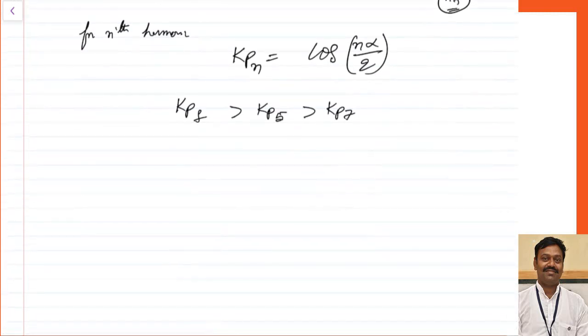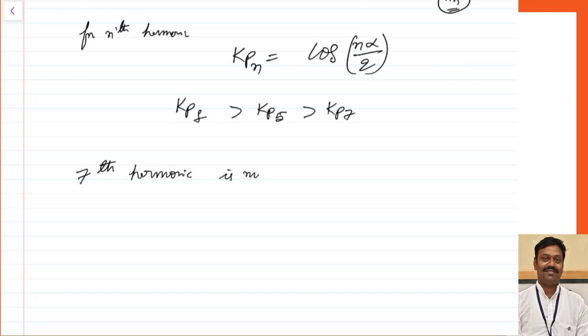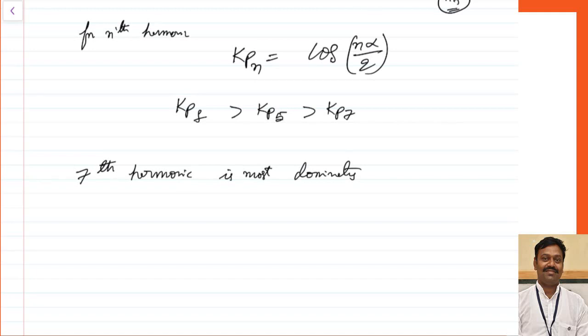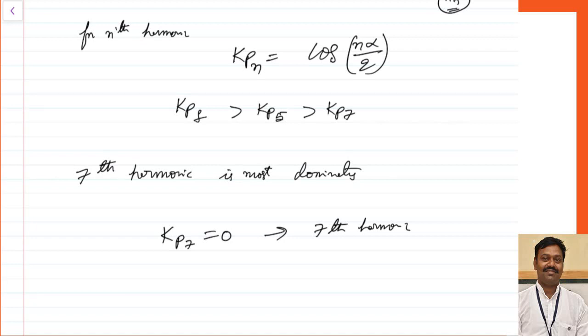As the order of harmonics increases, the cording factor will decrease. It is observed practically that in the induction motor, the 7th harmonic is most dominating. If you want to nullify the 7th harmonic, make Kp7 equal to 0 — automatically the EMF induced will be 0 and the harmonic component will be completely nullified. So Kp7 equals cos(7·α/2) should equal 0.